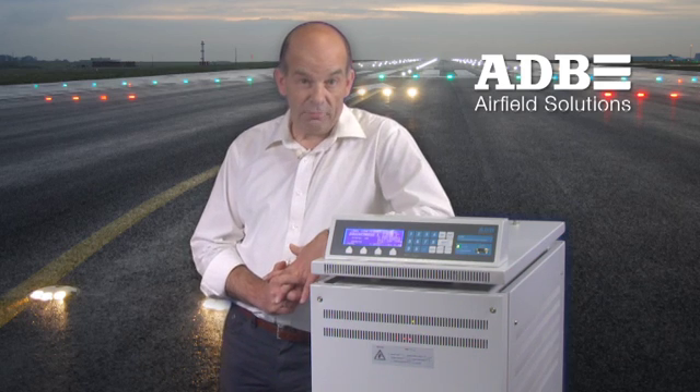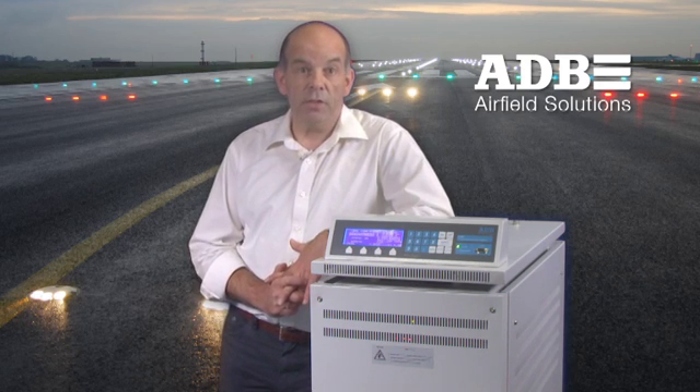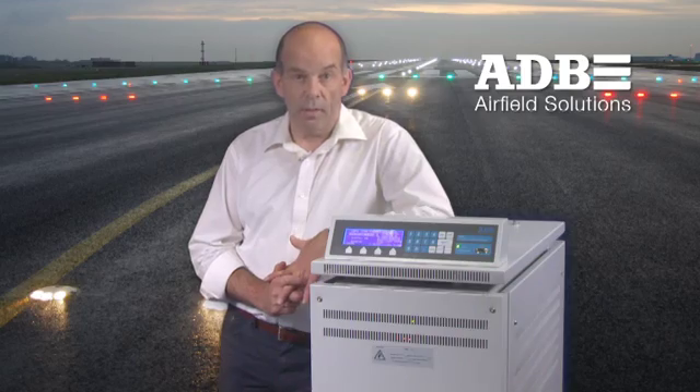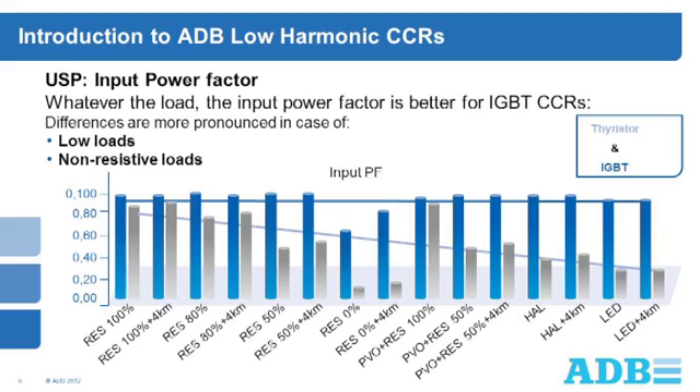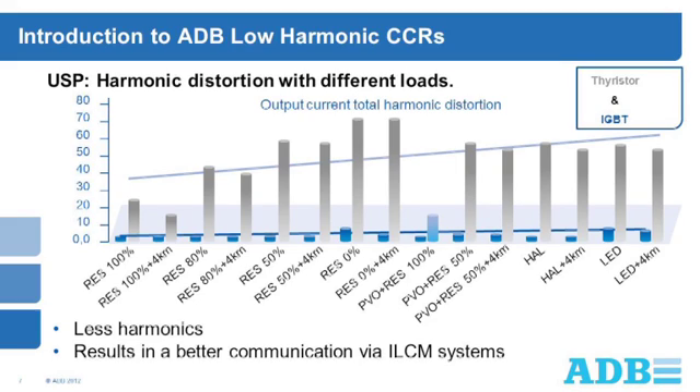Some of the key advantages of these CCRs are illustrated in these slides. Compared to normal operation conditions for CCRs, they use less apparent power for active or used power, which translates to a better power factor, especially at lower loads and lower brightness steps. Secondly, they offer low total harmonic distortion, which results in better communication via ILCM systems.